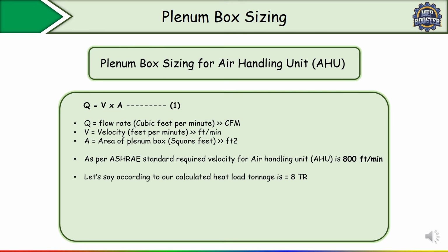Let's say according to our calculated heat load, the tonnage is 8 TR. Suppose you have calculated the heat load or cooling load value with the help of software, or manual calculation is also there. You have got 8 TR. As a rule of thumb we know that 1 TR needs 400 CFM, so we can easily convert this 8 TR into CFM. 8 TR needs 3200 CFM of air. So here we have got the flow rate value of 3200 CFM. Remember, this value you will get from the heat load calculation.